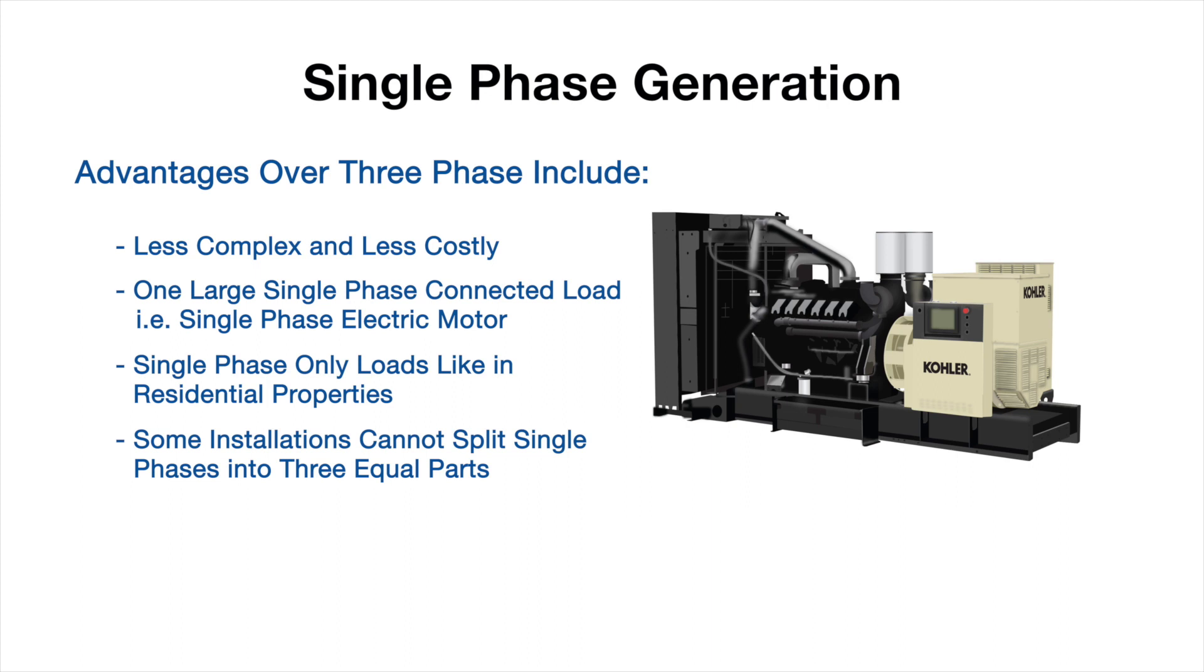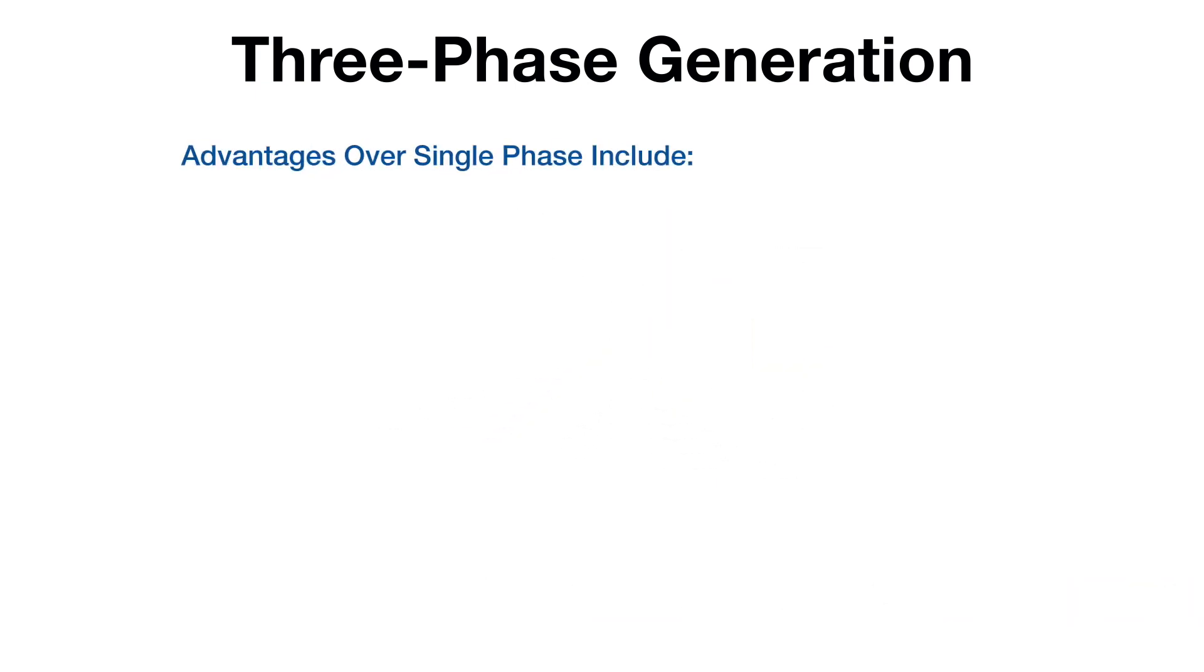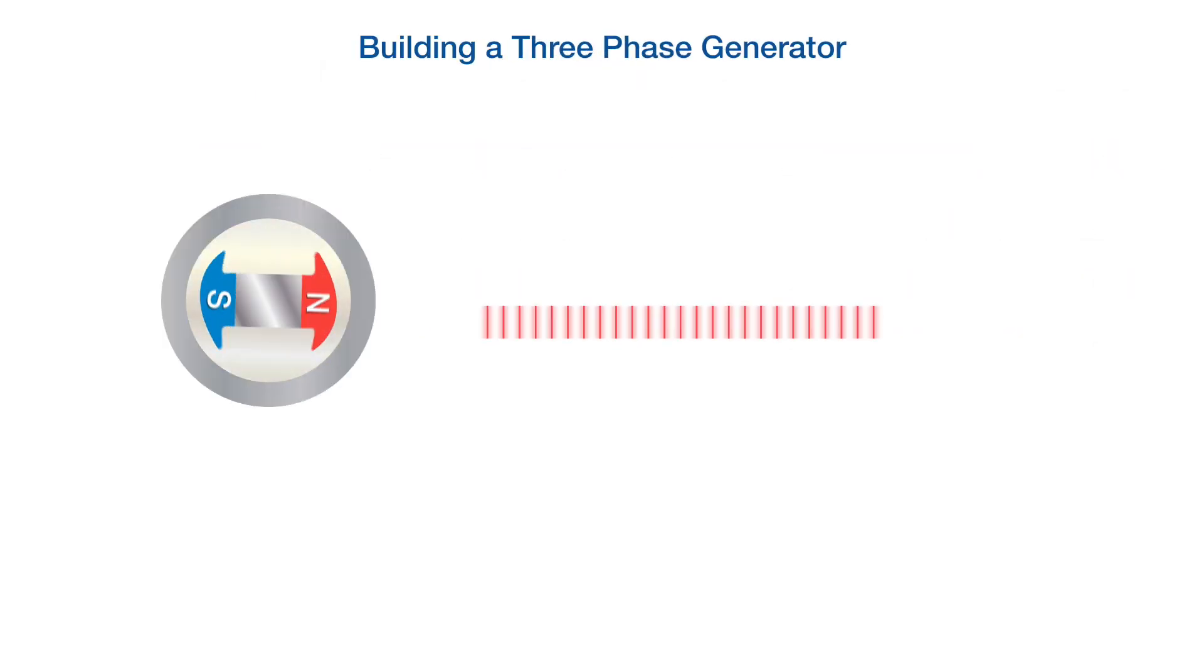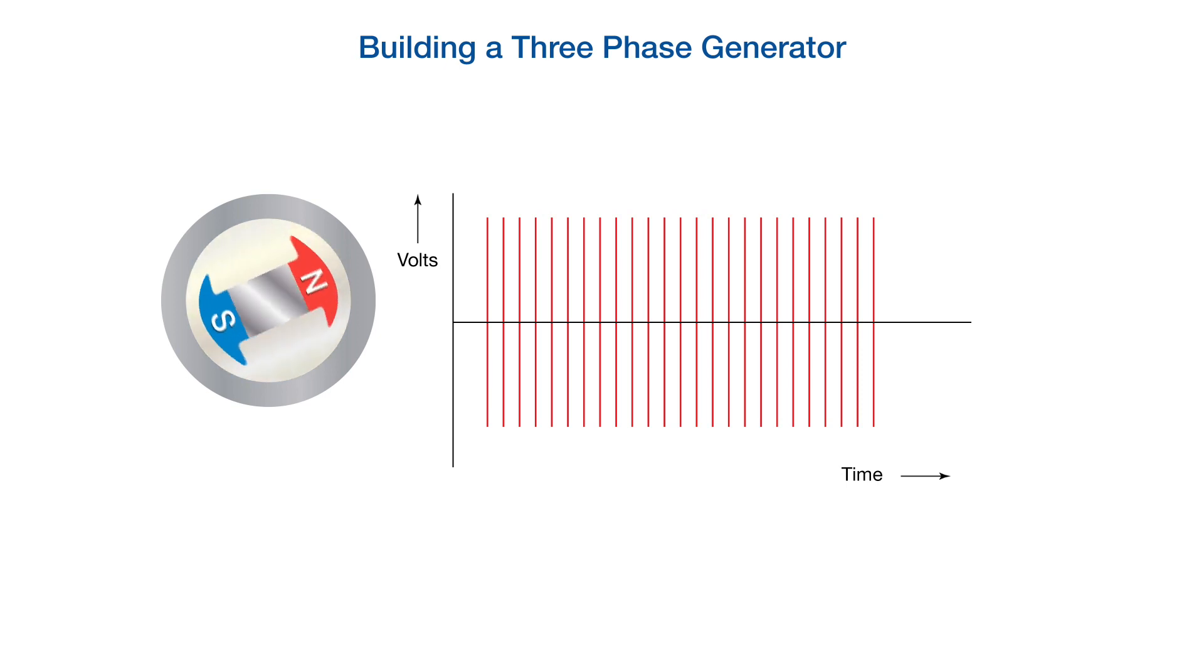While for some applications there are larger single-phase generators, the majority of loads above 15 kilowatts use three-phase generators. Advantages over single-phase include more compact, greater efficiency, and can manage greater loads. As indicated, a single-phase brushless generator with a rotating magnetic field has one set of coils wound into the stator. A three-phase generator is made possible by winding into the stator three sets of coils.